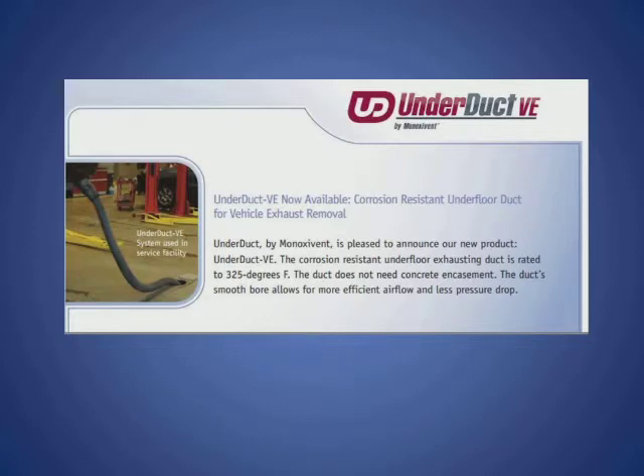Next, we're going to go into underduct VE. And underduct VE is probably one of our fastest growing specialty duct areas, because vehicle exhaust is very corrosive. You can get carbonic acid, nitric acid, sulfuric acid, all can condensate out in that ductwork from vehicle exhaust. And the fact that it's buried underground is important. And we also have a temperature requirement for it. We've done some testing, which we'll show you in a bit here, to make sure that we can do it.